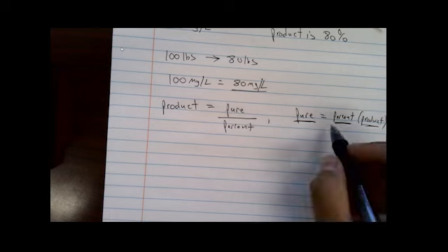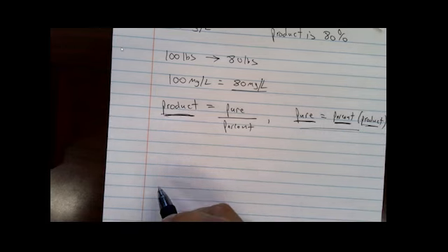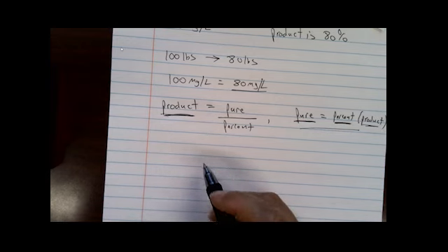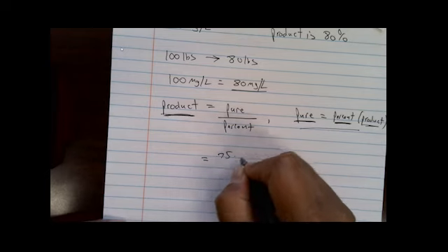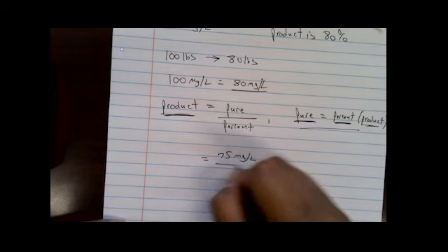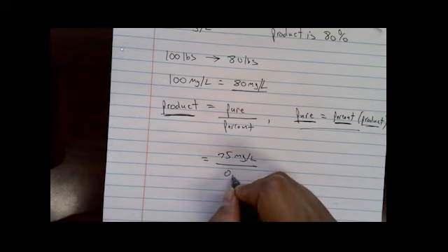So we're rearranging this formula to find how much product we need to achieve the 75 milligrams per liter. In that case, we have the pure 75 milligrams per liter, that's pure soda ash, right? Divide that by the percentage in decimal form, 0.8, to give us 75 divided by 0.8.